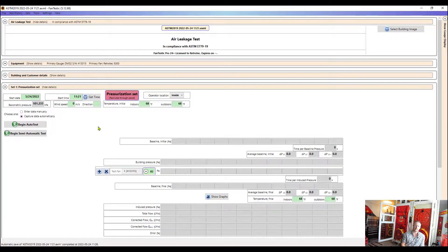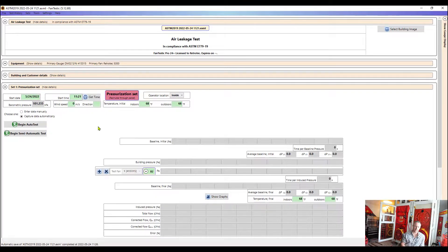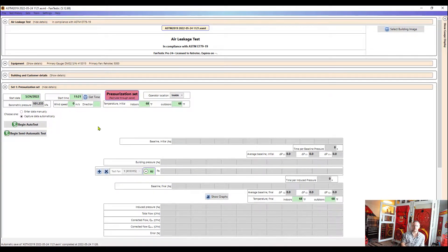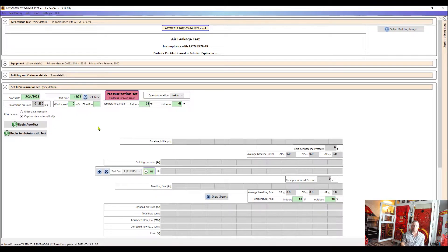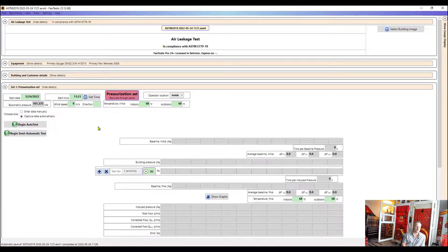The difference is with semi-auto, that's when we tell the software what we want to collect point by point. So for an auto test, we tell it how many points that we want to collect ahead of time and between what pressure. So for example, we could say I want to collect eight points between zero and 80 pascals. But we'll look into more of that next week.